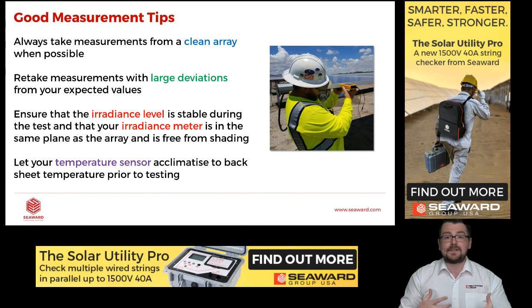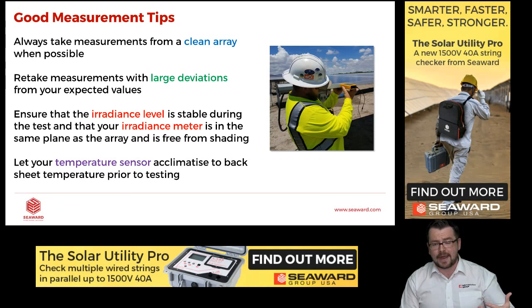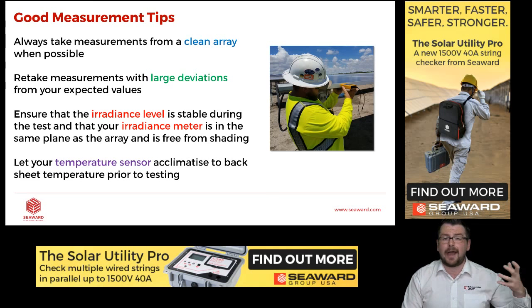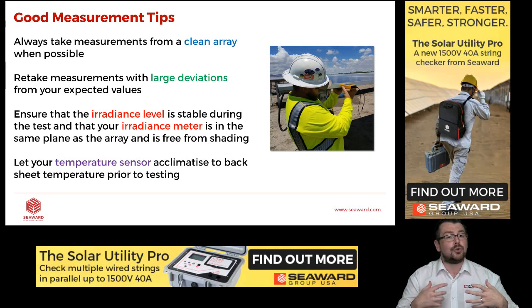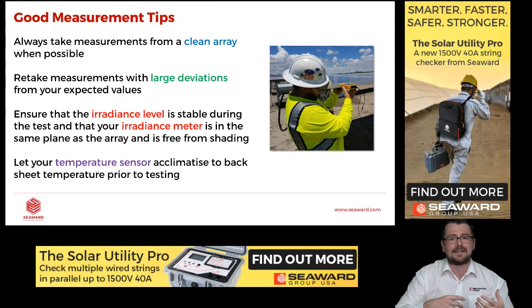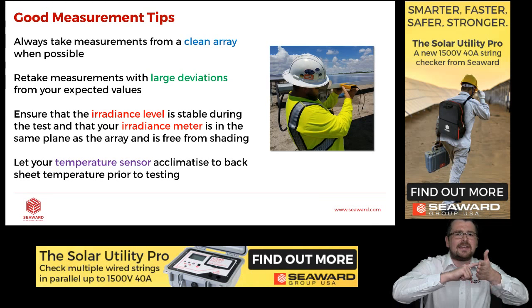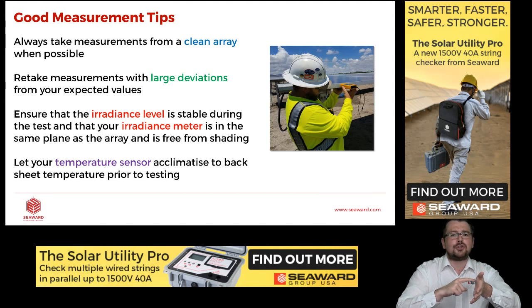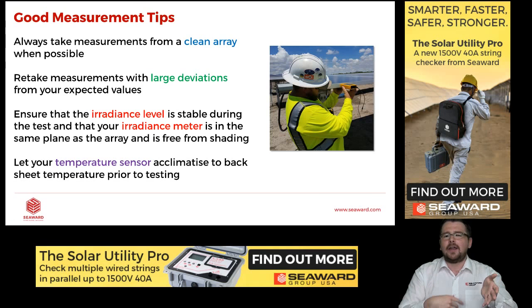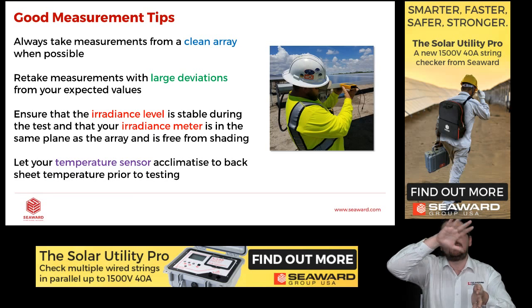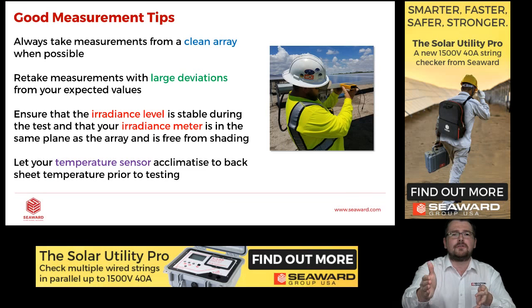So a couple of tips for taking good measurements. Always take measurements from a clean array. I think I described earlier how important that is. We should also retake measurements with large deviations. One of the biggest issues I find when I get PV data back from our clients is that they tell me, well, look at string number 17, I had a bad test. And then they go on to string 18, 19, 20. And I say, well, why didn't you retest 17? What if the clouds moved in the sky? What if someone walked in front of the panels?